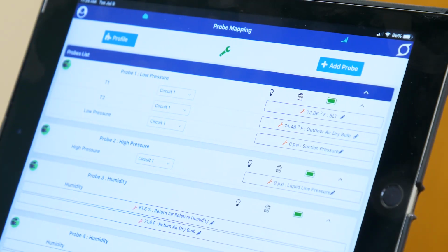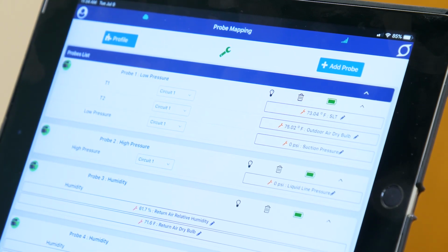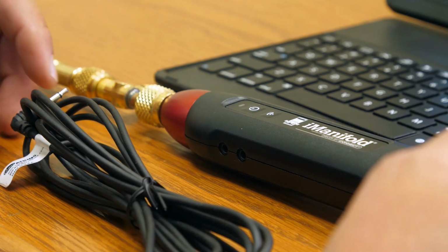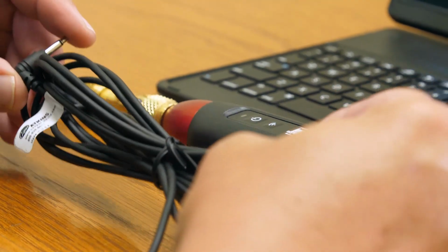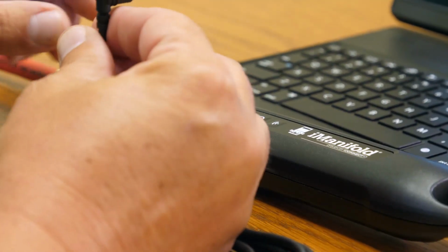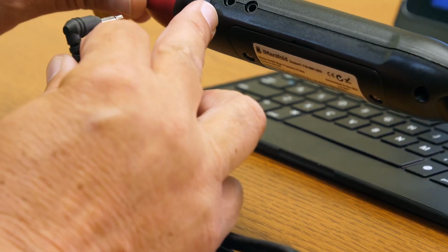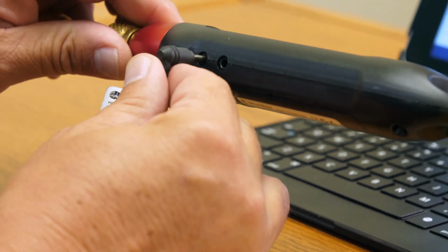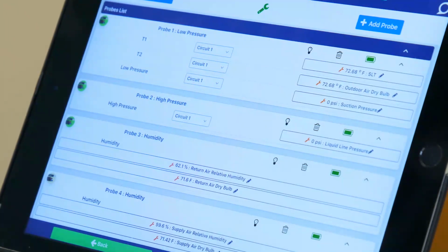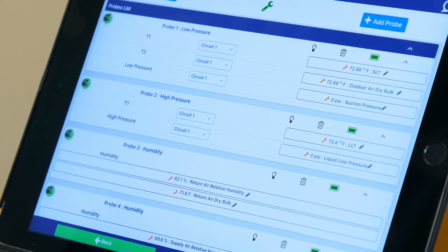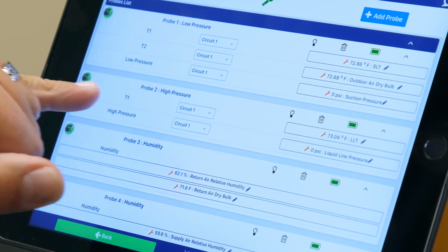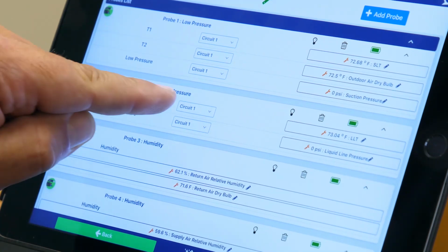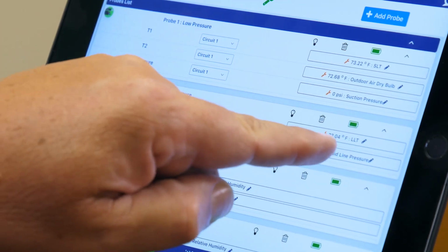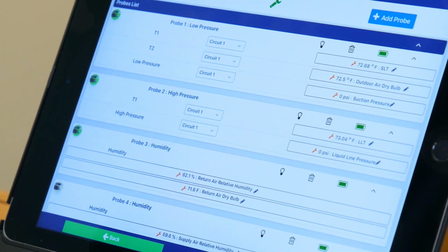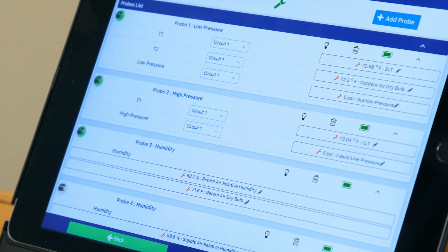Now we're going to move to the high pressure probe and put in our liquid line and our discharge line temperatures. So now moving to our high side probe, we're going to use another one of our 901M thermistors into port number 1, and we're going to use this for our liquid line temperature. Now plugging in our thermistor to T1 on our high side probe, we got T1, circuit 1, liquid line temperature. Now we're going to go ahead and use our T2 in there for our discharge line temperature.